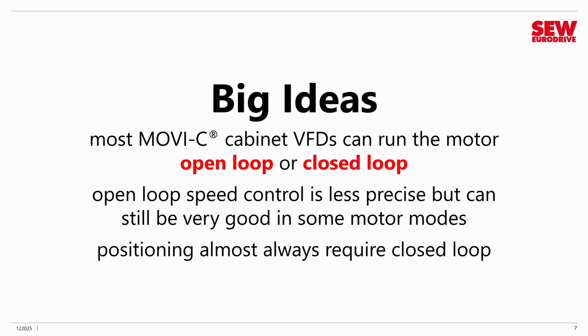Now, time for another big idea. Most MOVI-C cabinet VFDs can run the motor in one of two modes, what we call open loop or closed loop. What is this? Open loop simply means you don't have any kind of feedback from an encoder or a resolver. If you're in open loop mode, the VFD measures the current running through the motor, does some calculations, and can estimate what the motor speed is. Open loop speed control obviously is less precise than closed loop, but it can be very good in some motor modes. MOVI-C VFDs support certain control modes that are actually pretty good open loop.